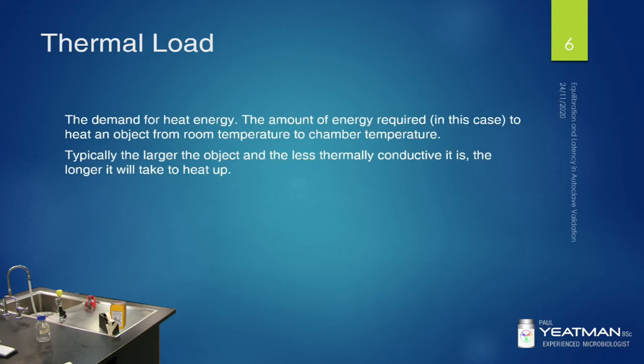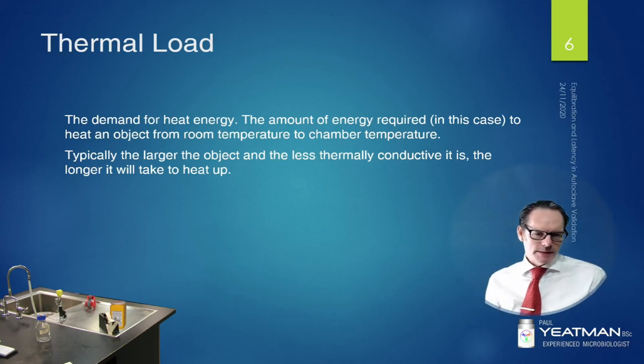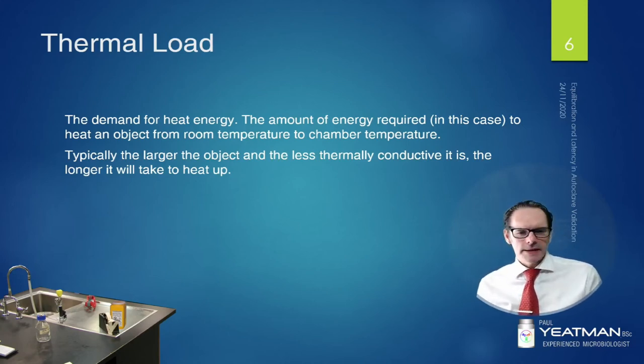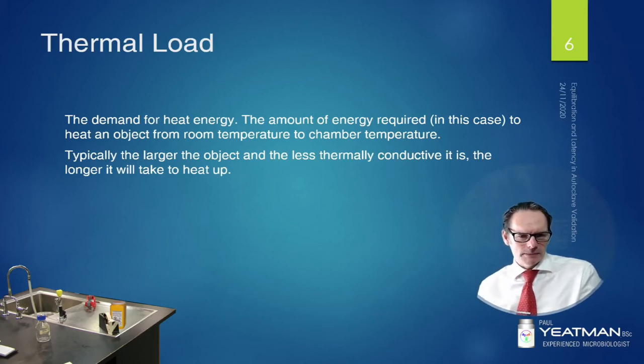Next up, thermal load. What is thermal load? That's pretty much the demand for heat energy — the amount of energy required to heat an object from room temperature, because hopefully you've started your autoclave cycle from rest, to the chamber temperature of 121 degrees Celsius. Typically the larger the object and the less thermally conductive it is, the longer it will take to heat up. So a piece of metal in an autoclave exposed to the steam should heat up faster than anything else because it has great thermal conductivity. Items within glass that contain liquid might heat up next fastest because water is a good conductor of heat, but there will be a little bit of air which doesn't conduct moist heat.